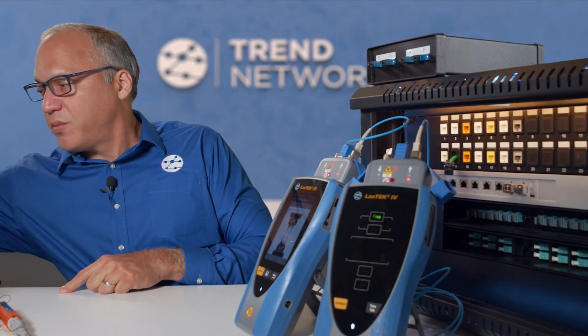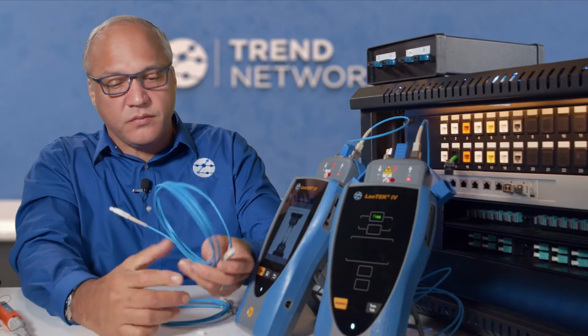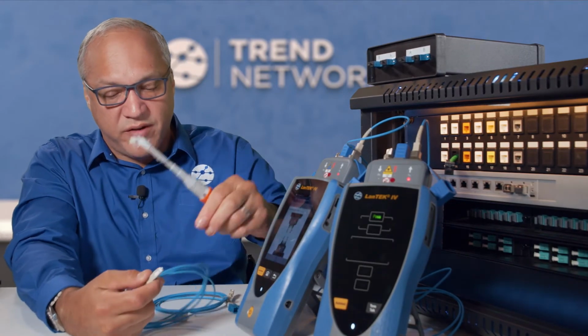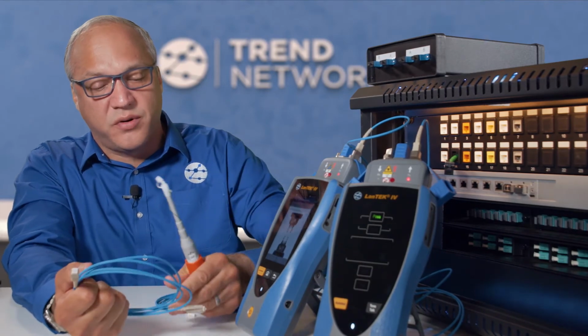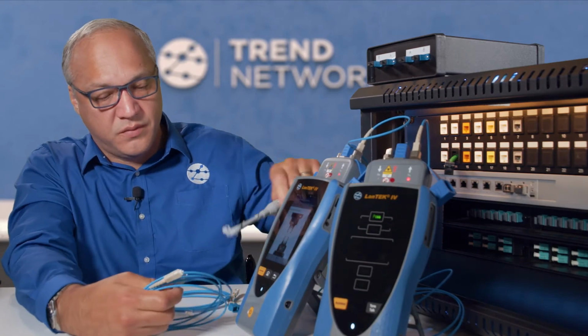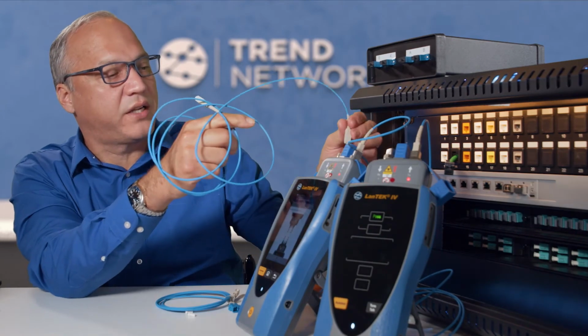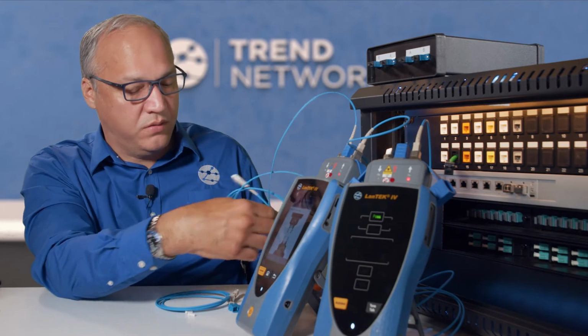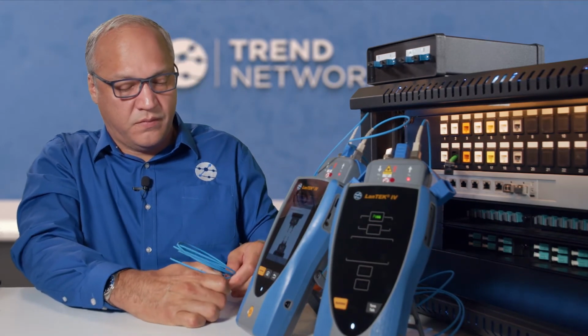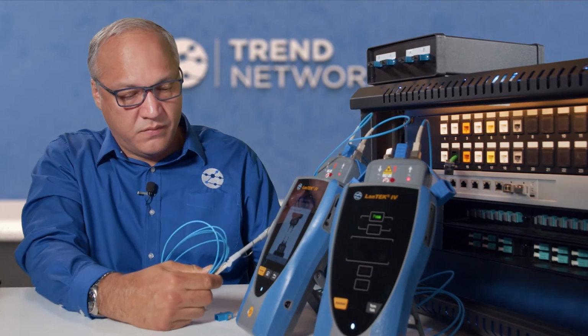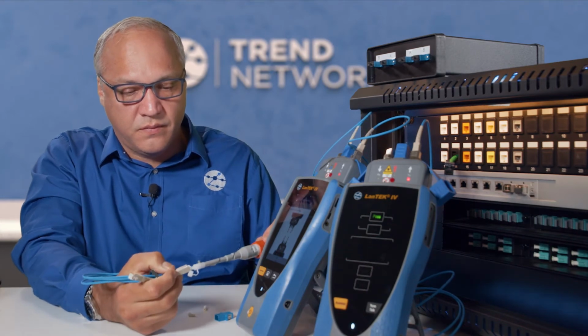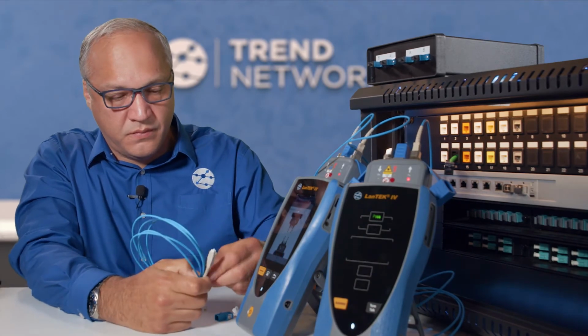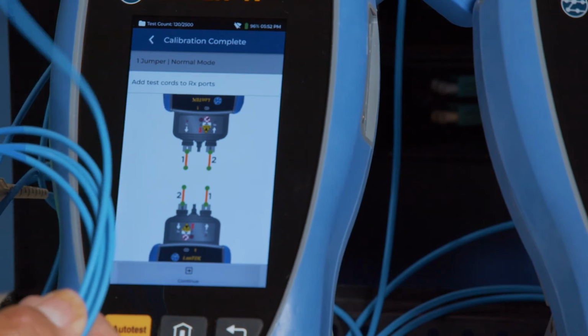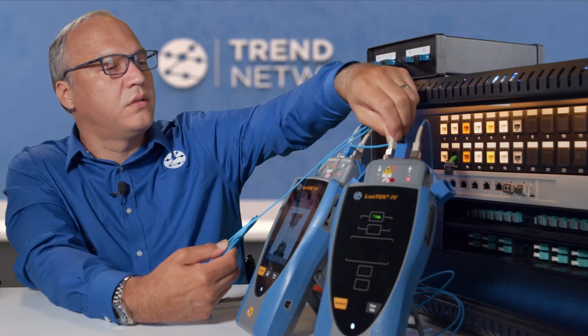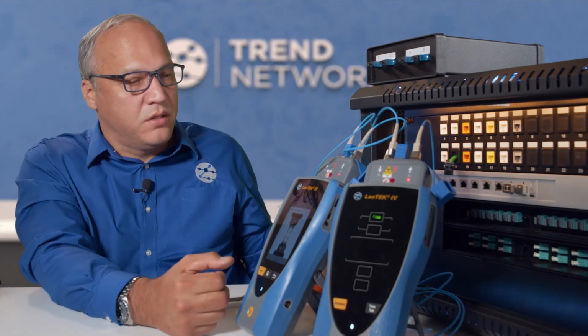So disconnect those, and then the next step would be to plug in the set of jumpers for our measurement phase. So it is a one jumper reference that we did, but we need to have a second set of jumpers after we perform the measurement. So we'll now connect the second set as shown. So now we have our 4 jumpers connected, and we're ready to test.